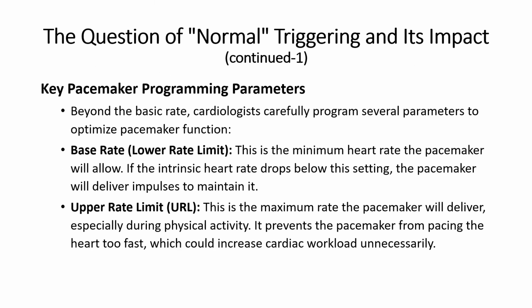Key pacemaker programming parameters. Beyond the basic rate, cardiologists carefully program several parameters to optimize pacemaker function. Base rate, lower rate limit. This is the minimum heart rate the pacemaker will allow. If the intrinsic heart rate drops below this setting, the pacemaker will deliver impulses to maintain it. Upper rate limit, URL. This is the maximum rate the pacemaker will deliver, especially during physical activity. It prevents the pacemaker from pacing the heart too fast, which could increase cardiac workload unnecessarily.